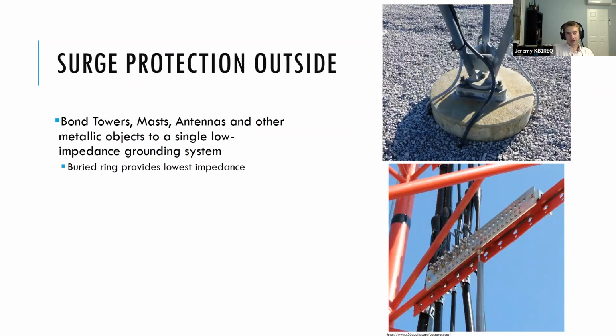So what's our strategy outside? Our strategy outside is essentially bonding anything that's metallic to ground. So everything that's related to our antenna support structure, towers, masts, antennas themselves at the appropriate locations should be bonded, using some of those practices we talked about in the first slide, to a single low impedance ground system. The best we can get here is a ring that covers the entire area of that tower, of that communications facility.